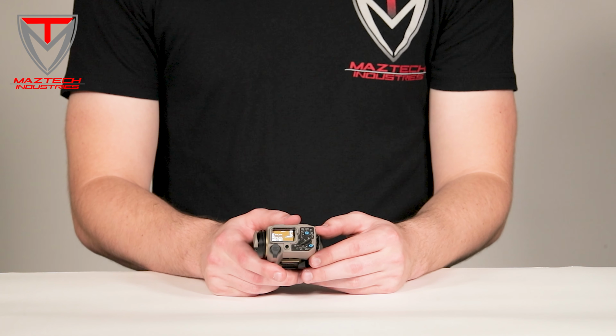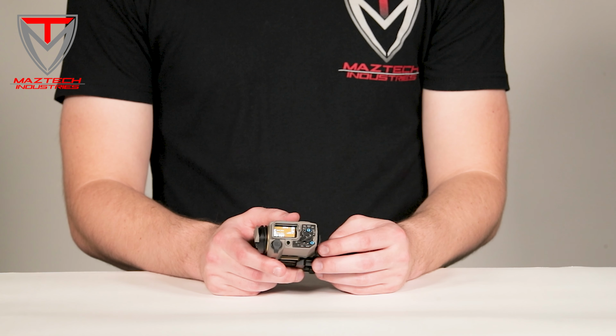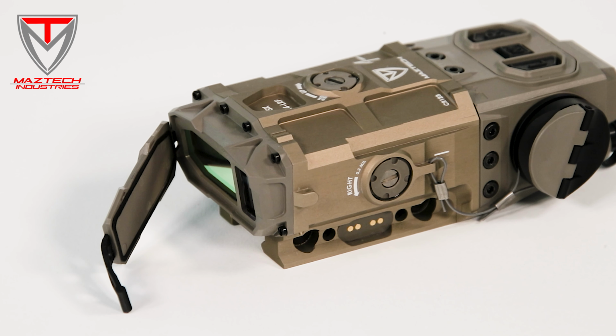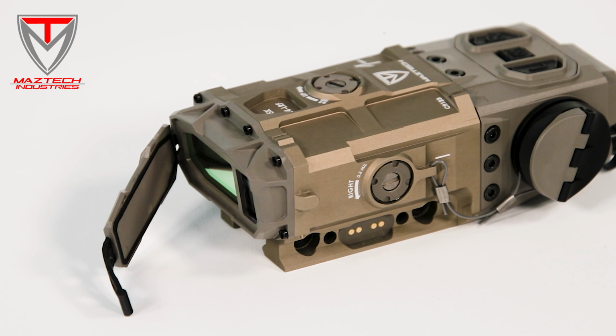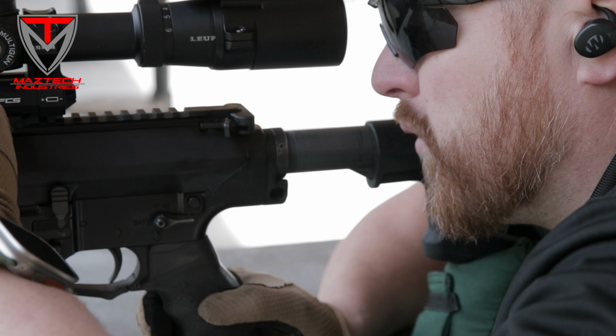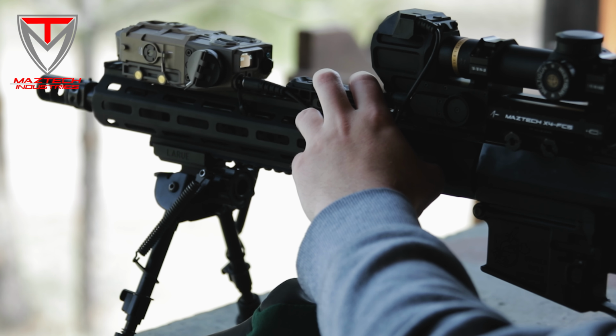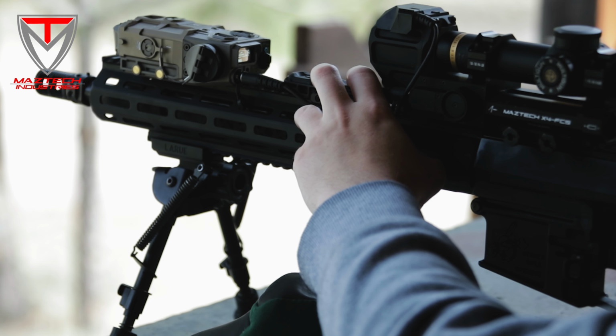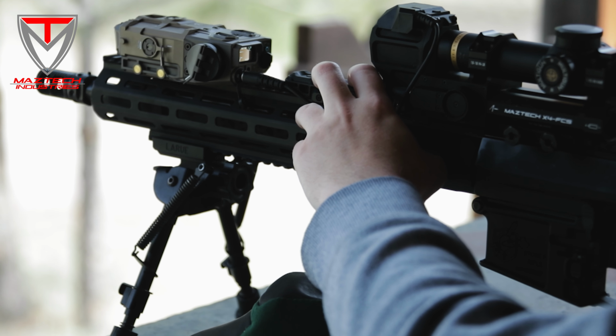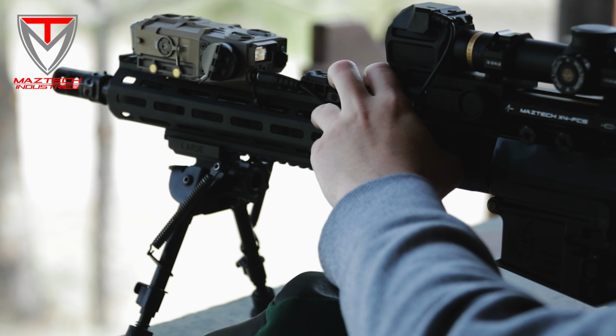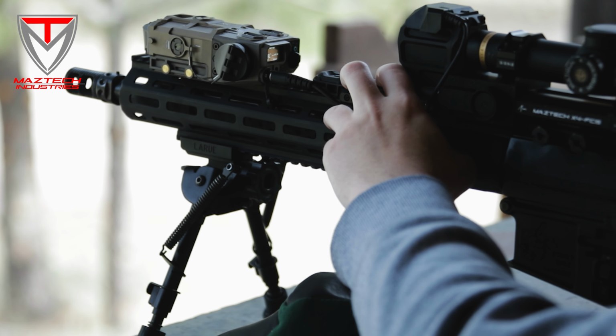The LRF contains Class 3R lasers, emitting both invisible and visible radiation. Keep the aperture cover closed and latched when not in use. Avoid direct eye exposure to the laser beams, as serious injury may result. Review all laser safety guidelines provided in the manual's appendix before operating the device.